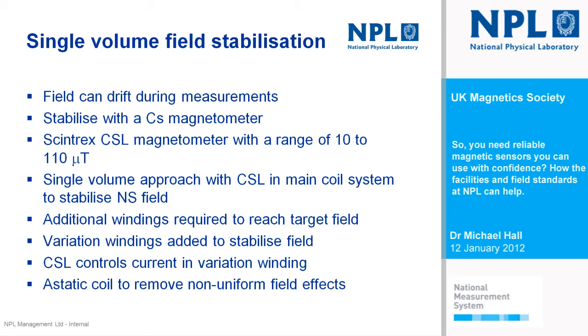We will have the CSL magnetometer in the cancellation system, so when we want to generate a field, we will use additional windings that need to be placed on the north-south axis coil formers. There will be 2 of them. One will be used to generate that field target that we require, and then there will be a variation winding that will be used to stabilise it, and the current in that variation winding will be controlled by the output of the cesium magnetometer. Hence we achieve the stabilisation control of the field through the current, and that's from the output of the magnetometer through a phase detector which drives the current.